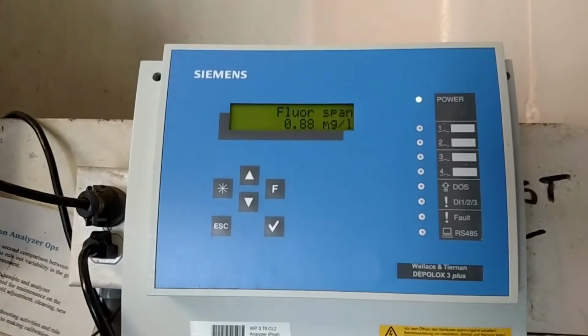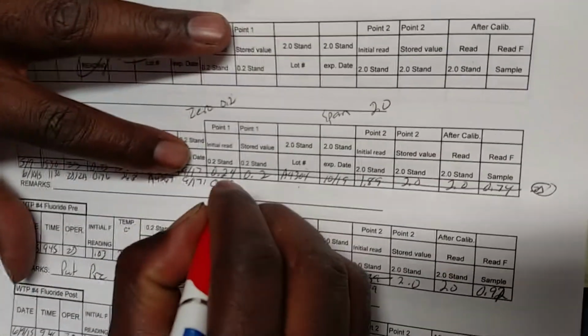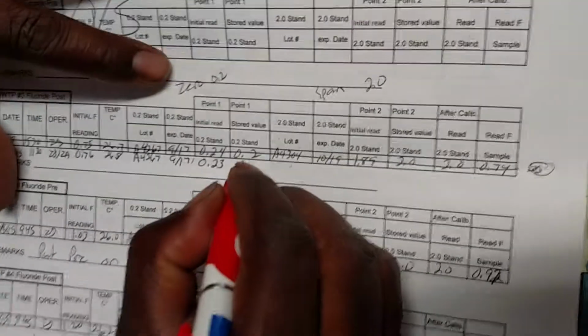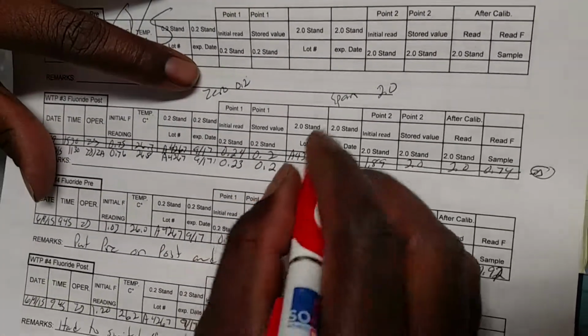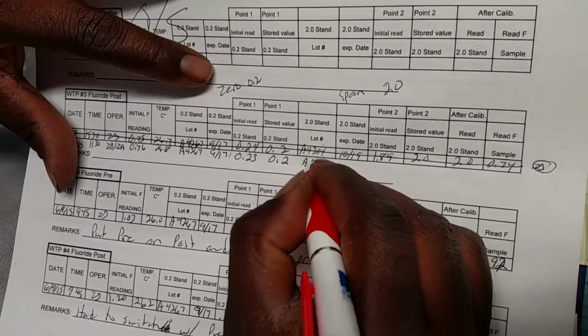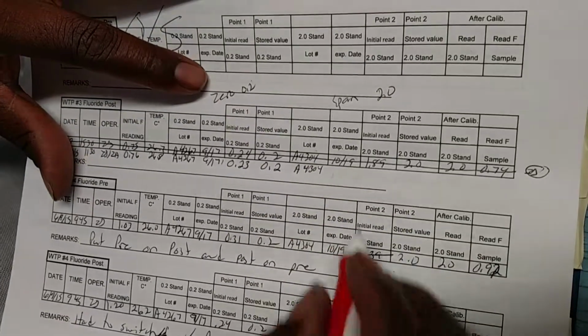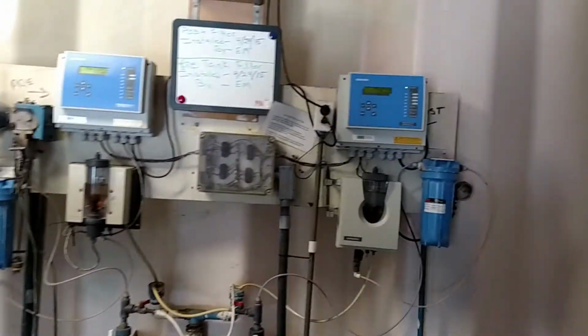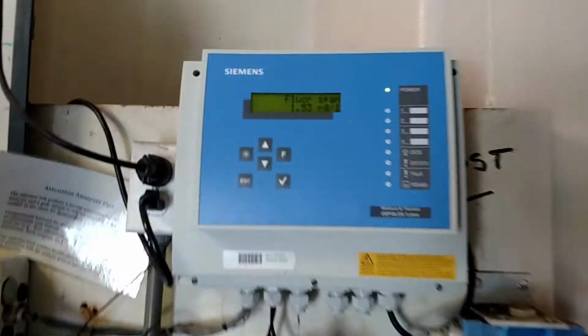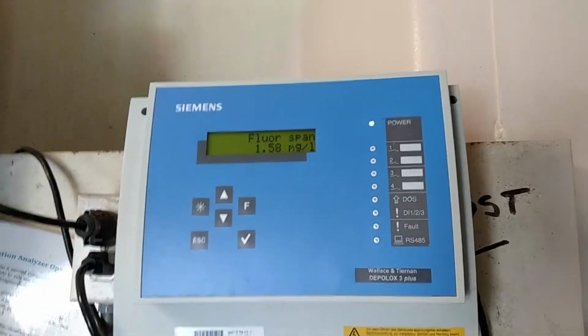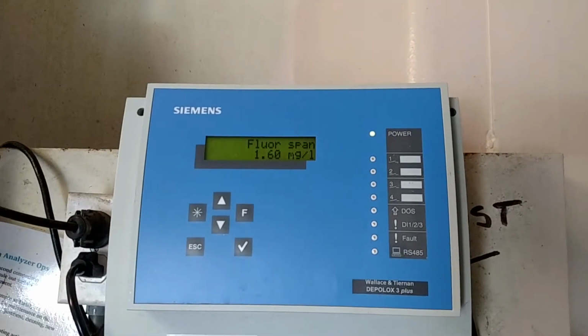And what I need to do now, as far as my numbers, is write in that it was a 0.23, and then we calibrated it to a 0.2. And then I'm going to write my lot number for my standard for the 2.0 and the expiration date. And we're just going to wait now for that to stabilize. It's going up fairly good. Usually if it goes up or down fairly quickly, that normally indicates a pretty good probe.